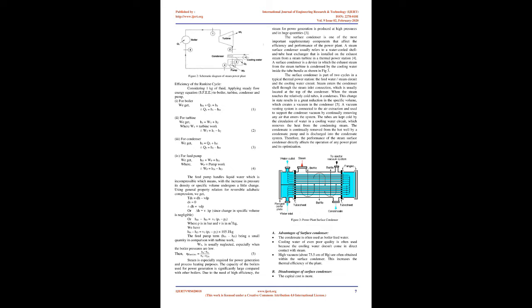The condensate is continually removed from the hot well by a condensate pump and is discharged into the condensate system. Therefore, the performance of the steam surface condenser directly affects the operation of any power plant and its optimization. Advantages of surface condenser. The condensate is often used as boiler feed water. Cooling water of even poor quality is often used because the cooling water doesn't come in direct contact with steam. High vacuum, about 73.5 cm of Hg, is often obtained within the surface condenser. This increases the thermal efficiency of the plant.